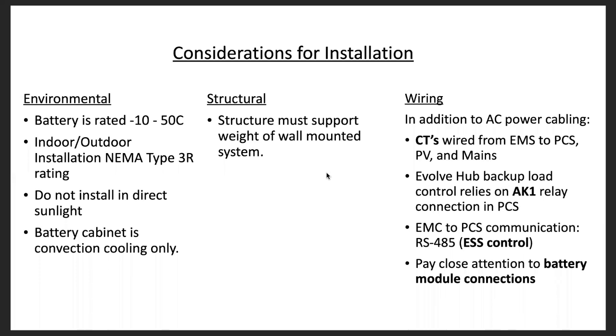Wiring considerations for installation. In addition to the AC conductors, there are CTs that you've got to wire between the hub and obviously the service panel, the battery itself, and the PV, which is internal to the hub. If those CTs need to be extended, you've got to make sure that you use the right spec wire and account for that. The Evolve Hub, the backup load control, relies on the AK1 relay connection in the PCS, and this is a minor detail that's covered in the installation manual. It's just listed here as a note to be aware of. In addition to standard conductors, this conductor as well as the battery communications cable are all provided with the system.